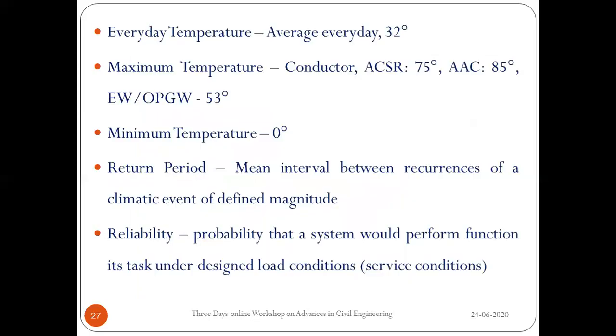Insulators play a major role in transmission line towers. For temperature parameters in the Indian scenario: average everyday temperature is 32°C; maximum conductor temperature is 75°C for ACSR and 85°C for AAC; earth wire maximum is 53°C; minimum temperature is 0°C in tropical regions, or −5°C in snowy regions.